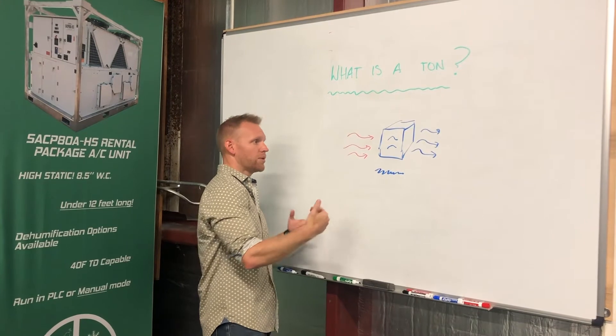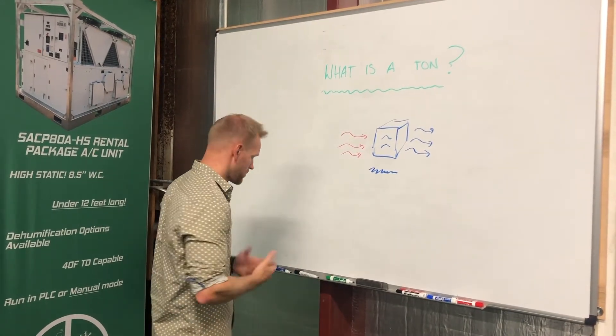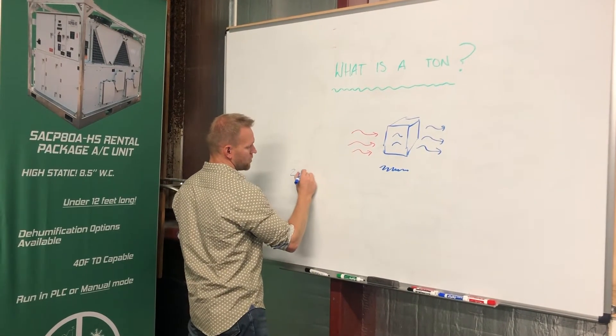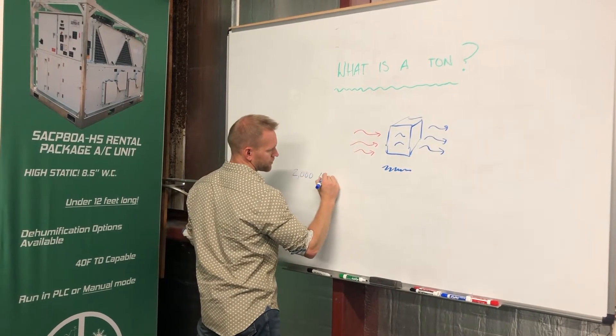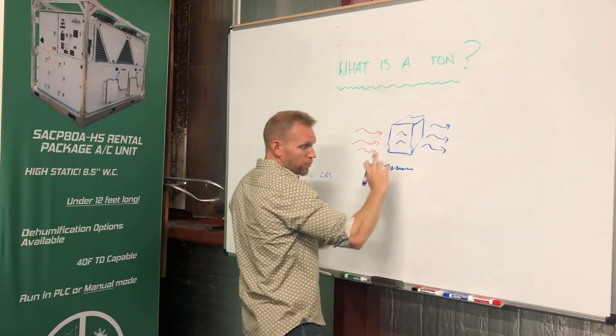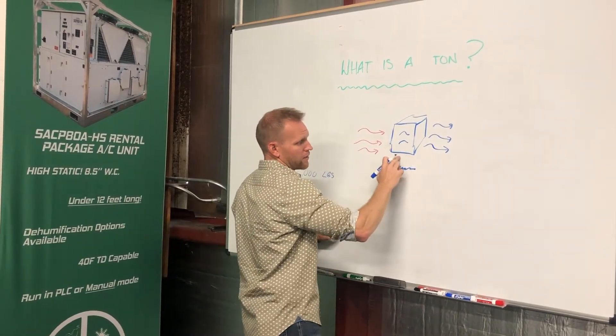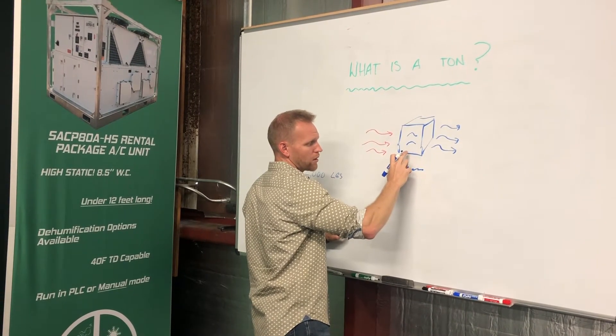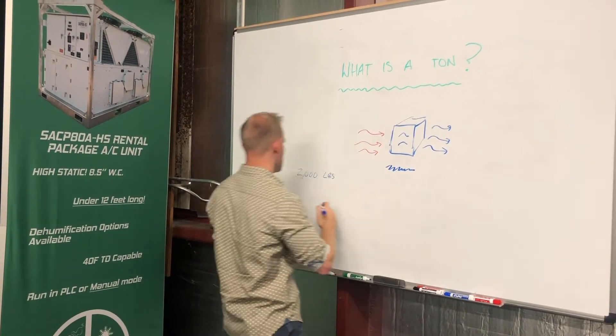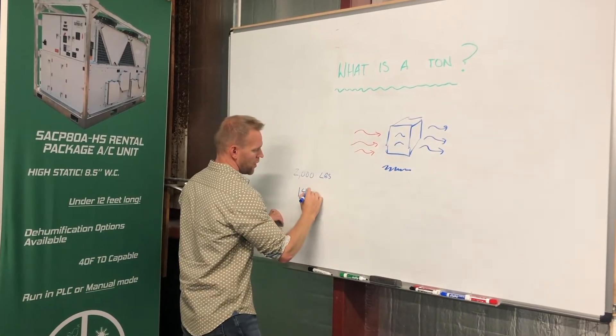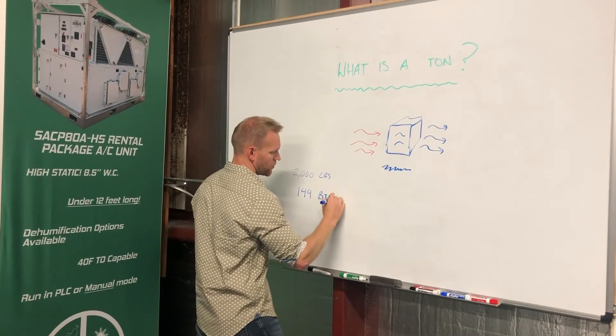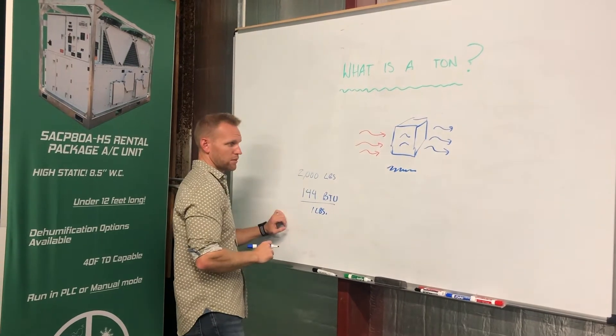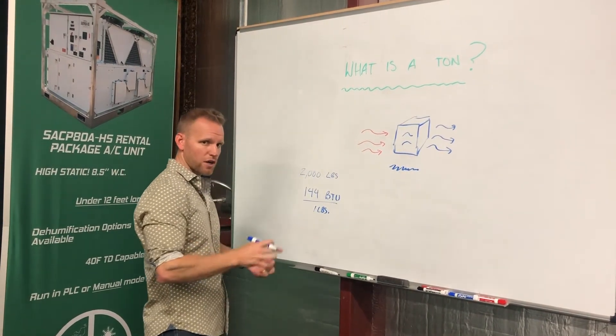Let's go a little bit more in depth and talk about what that means. We know that a ton is equal to 2,000 pounds. But we also know that the phase change — the energy required to phase change one pound of water from ice to its liquid state — is 144 British thermal units per one pound of water.